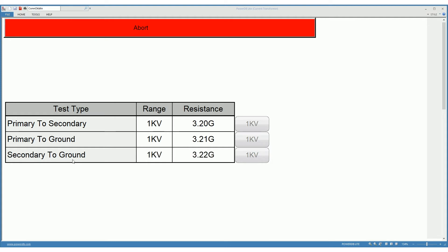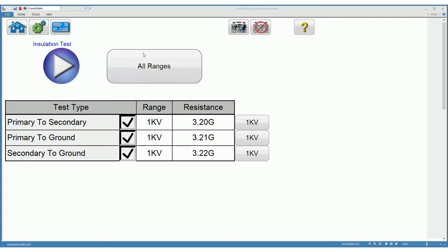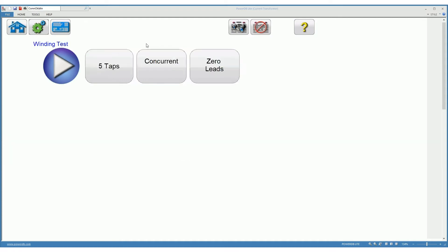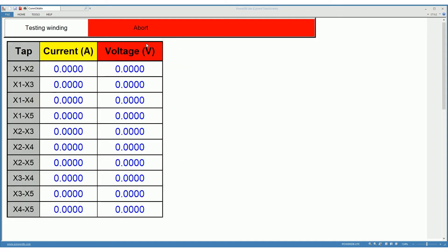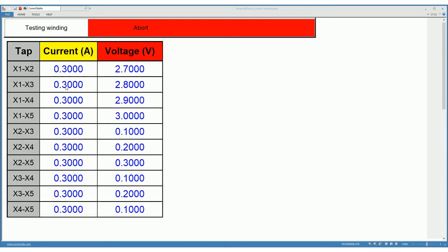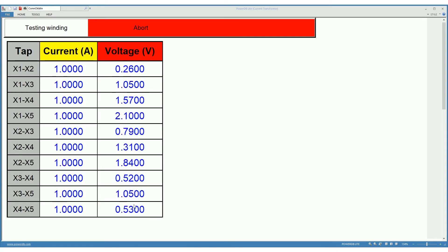Followed by the winding resistance tests where we are injecting a regulated current, reading the voltages, and calculating the corresponding resistances.